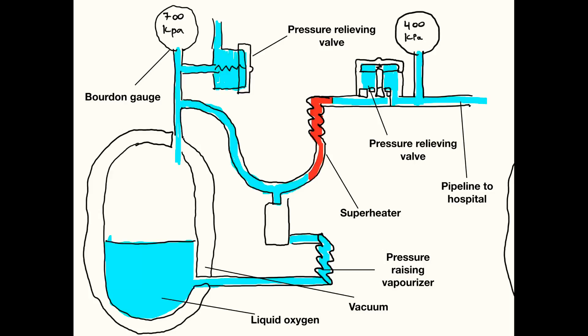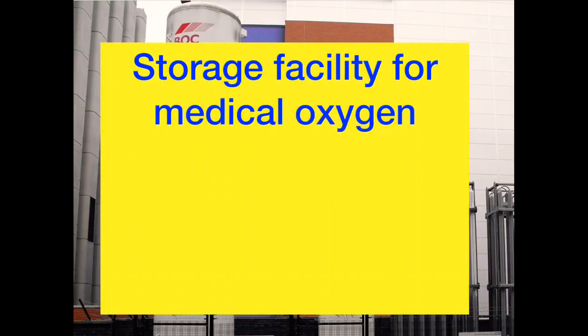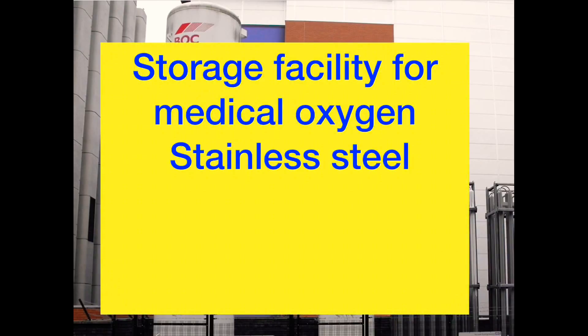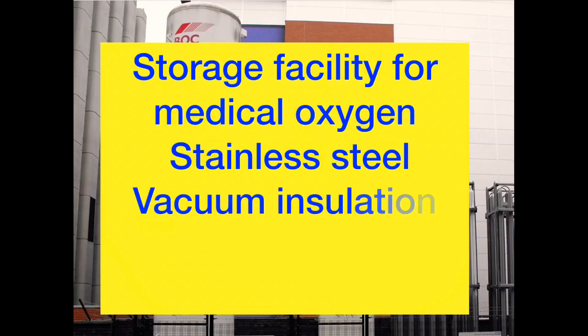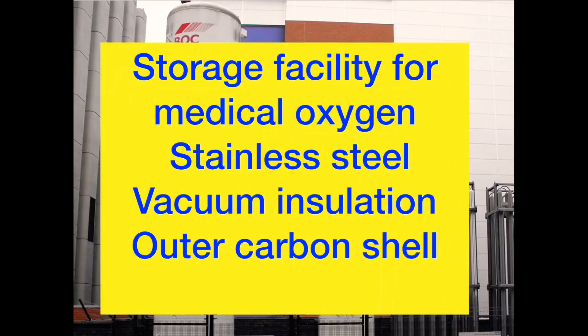The vacuum insulated evaporator, or VIE for short, is used as a storage facility for medical oxygen. It is a large stainless steel tank insulated by a vacuum to around minus 160 degrees centigrade, with an outer carbon shell. It rests on a weighing scale.